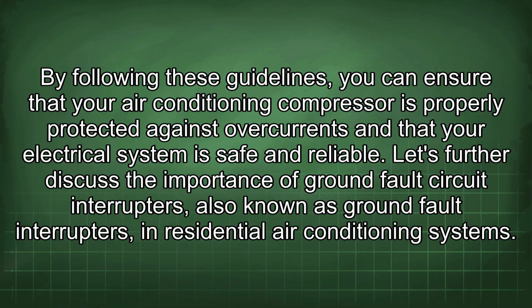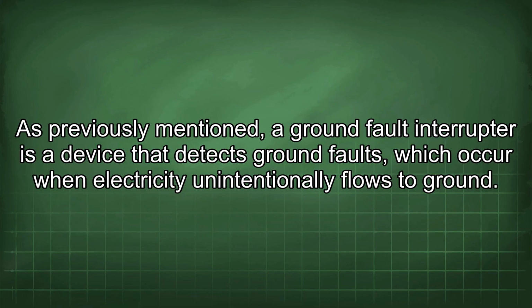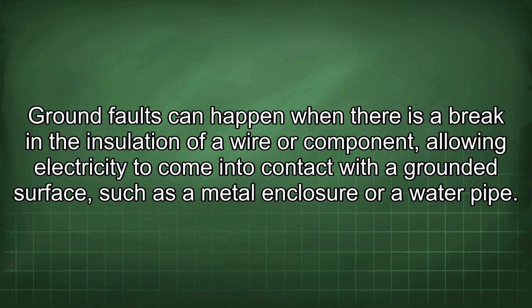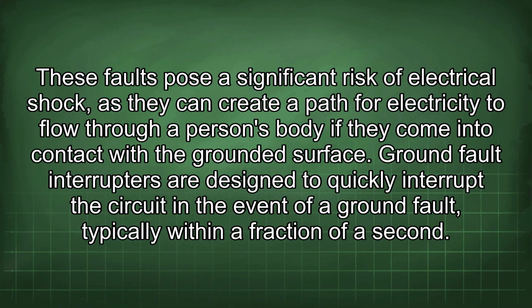Let's further discuss the importance of ground fault circuit interrupters, also known as ground fault interrupters, in residential air conditioning systems. As previously mentioned, a ground fault interrupter is a device that detects ground faults, which occur when electricity unintentionally flows to ground. Ground faults can happen when there's a break in the insulation of a wire or component, allowing electricity to come into contact with a grounded surface, such as a metal enclosure or a water pipe. These faults pose a significant risk of electrical shock, as they can create a path for electricity to flow through a person's body if they come into contact with the grounded surface.